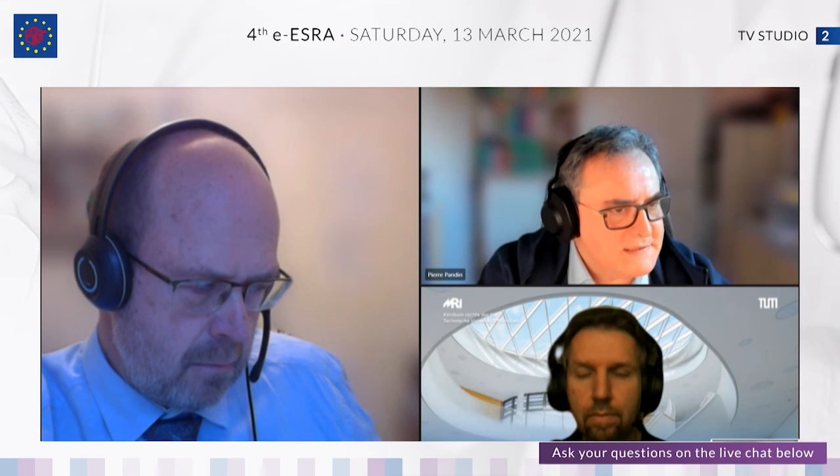So we had two options. First, to use, as you are doing, classical pumps with syringe, but Pajunk has developed a connection system which makes it possible to connect NRFit to a non-NRFit pump at the moment, because our plan is to replace our park of non-NRFit PCA pumps by NRFit PCA pumps. But it is expensive, and we calculated we need a 2 year period to switch all our pumps. So for now we are working with this connector developed by Pajunk.